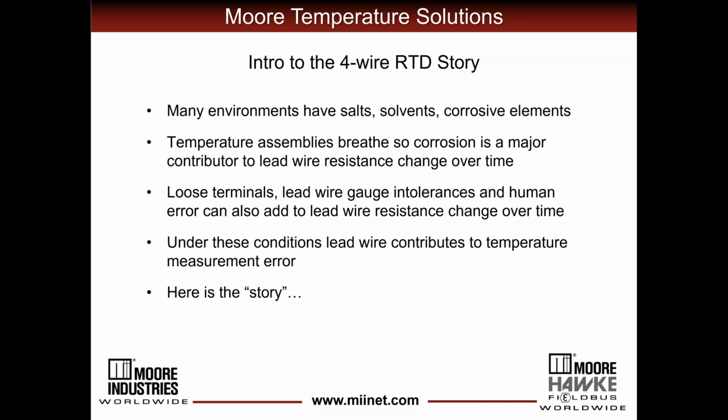If you individually have not studied the technology of RTDs, but you're aware that RTD extension wiring is just standard copper wiring, you may believe that the copper extension wiring does not introduce error into any of the RTD measurements. RTDs are resistors, variable resistors with temperature. And copper wire also has resistance. So copper wire can cause significant errors in the RTD measurement.